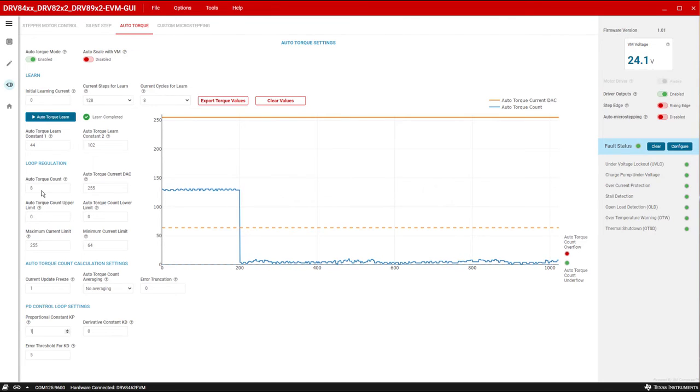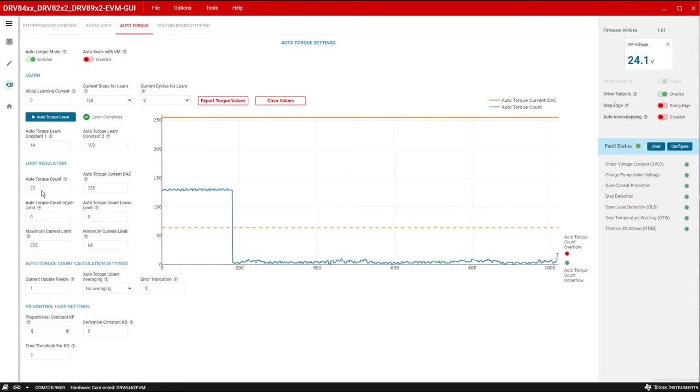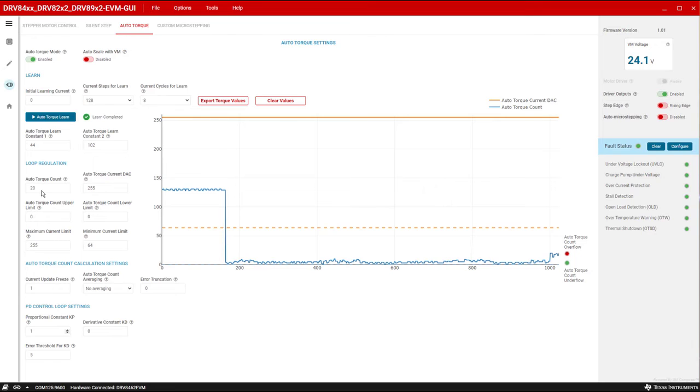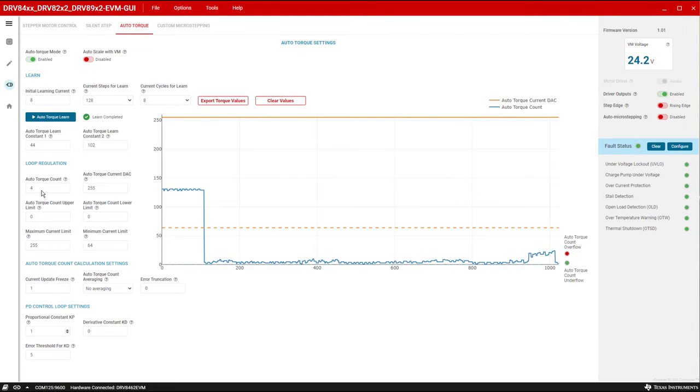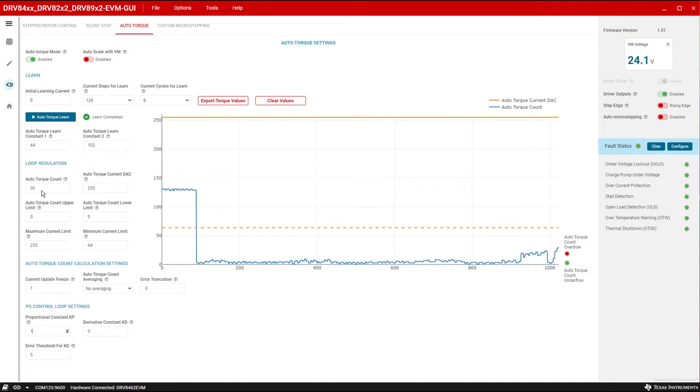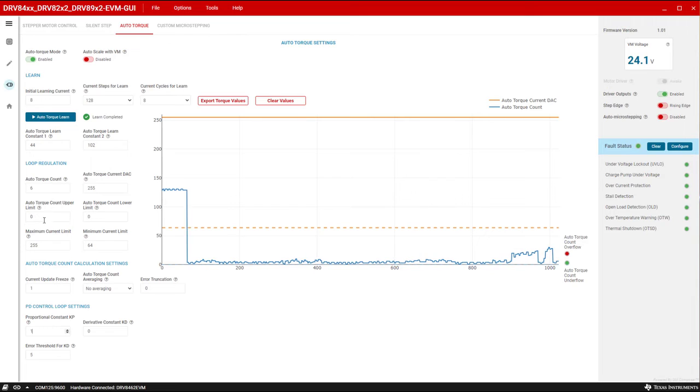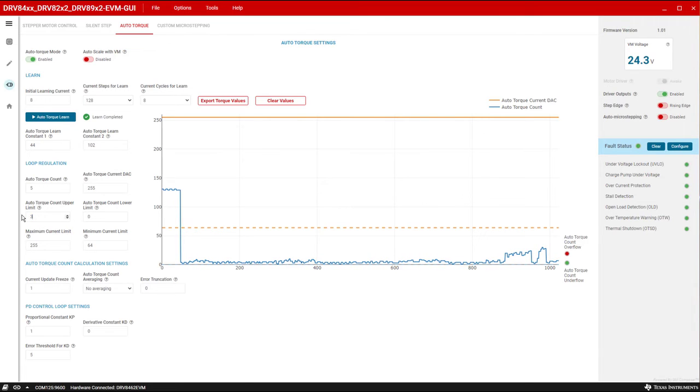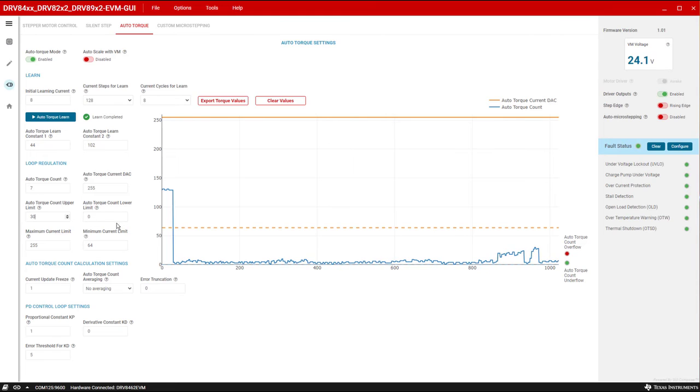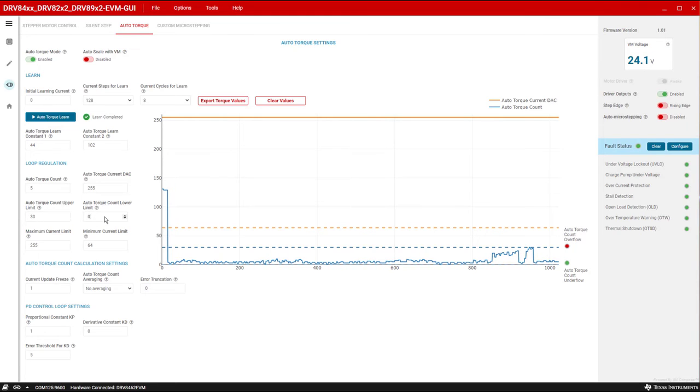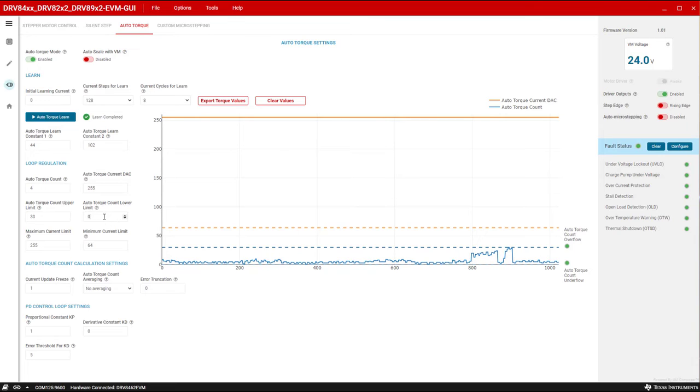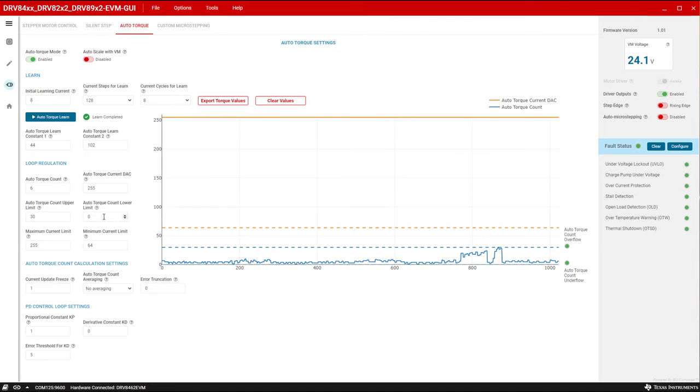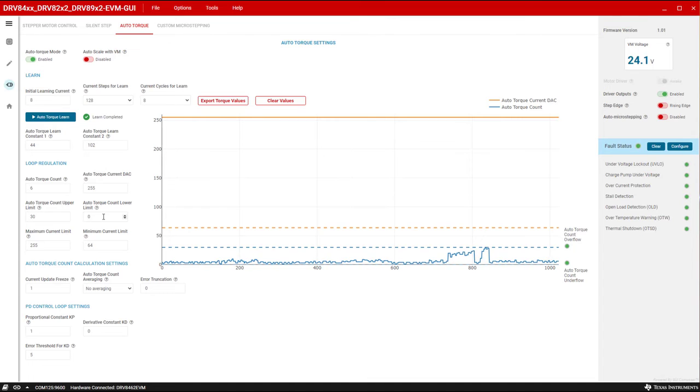To identify and set up these parameters, observe the auto torque count values while loading the motor close to its maximum load torque in the application. Input this value to auto torque count upper limit. The auto torque count lower limit can be the same value with no hysteresis or a value lesser than the upper limit based on the desired hysteretic band of operation. In this example, we'll use a hysteretic band of 10.